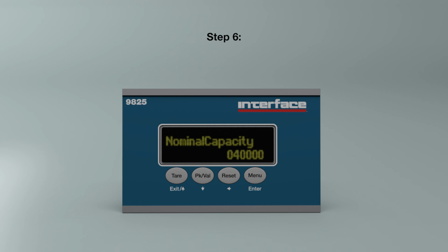Step 6. After confirming the nominal capacity value, the nominal capacity menu item will be displayed again. Press the menu key to scroll right to the next menu item called Display Resolution. Press the peak and valley key to enter the Display Resolution submenu. For this example, we will set the display resolution to 1. Use the reset key to scroll through the options until 1 is displayed. Press the menu key to confirm the selection.